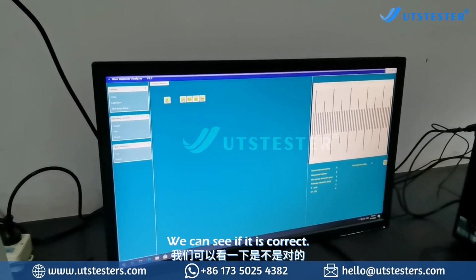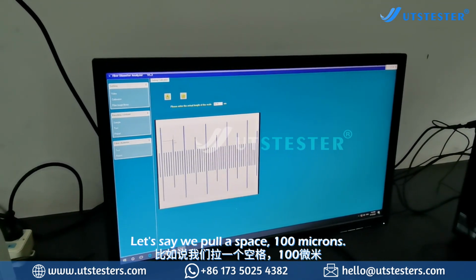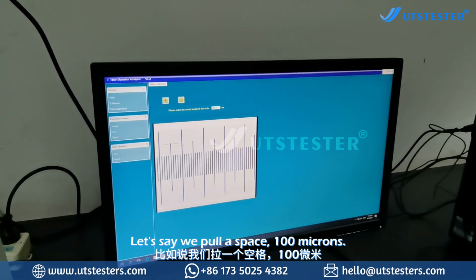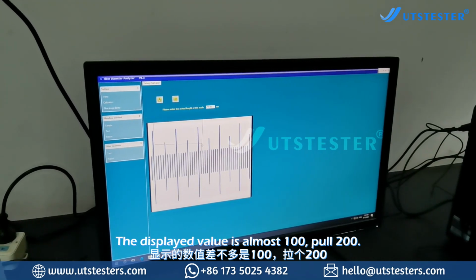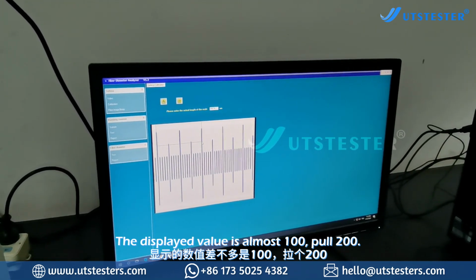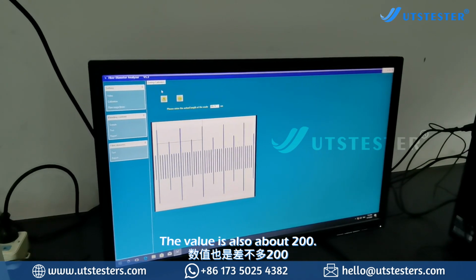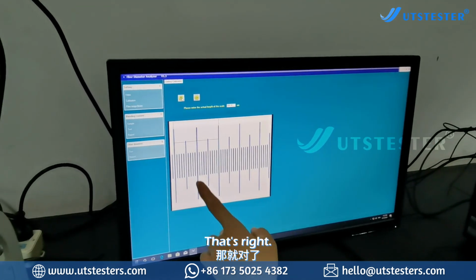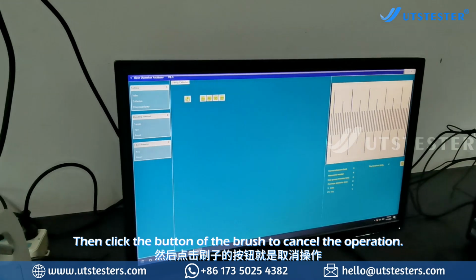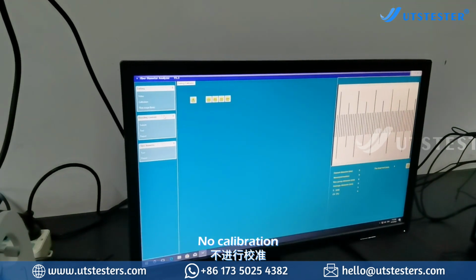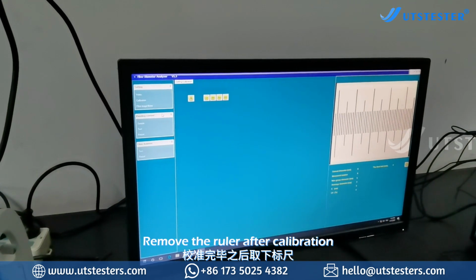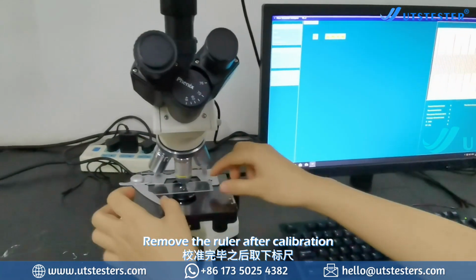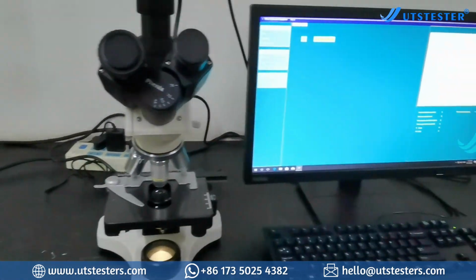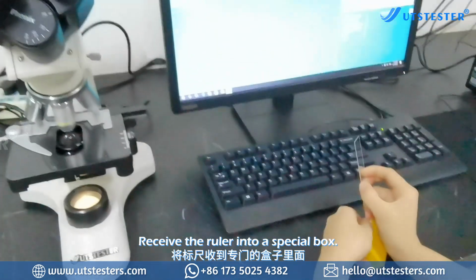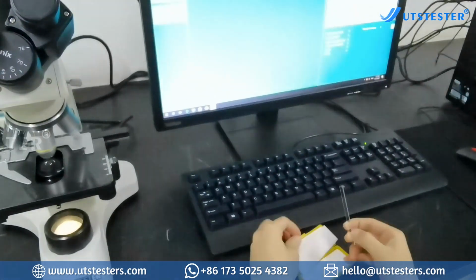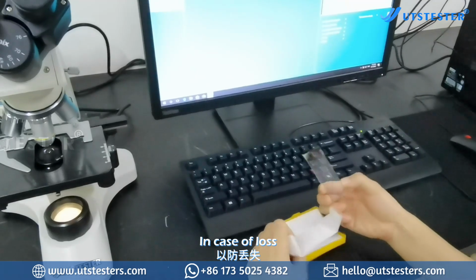We can see if it is correct. Let's say we pull a space of 100 microns. The displayed value is almost 100. Pull 200. The value is also about 200. That's right. Then click the brush button to cancel the operation. No calibration is needed. Remove the ruler after calibration. Put the ruler into a special box in case of loss.